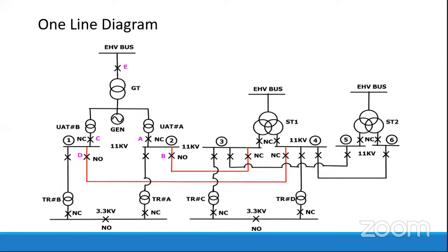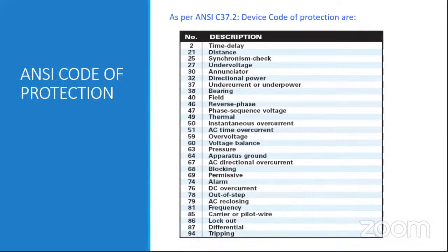For every protection, there are ANSI codes defined as per the IEEE standard. Here you can see the ANSI codes for the protections or the protection devices. ANSI code 2 is for time delay, 21 for distance, 25 for synchronization check. Synchronization check means if two sources are feeding the network in parallel, there should be a synchronization check relay that checks the synchronization of both sources. If there is a mismatch, it should isolate the faulty or unhealthy source, so that there is no interruption in the power supply.